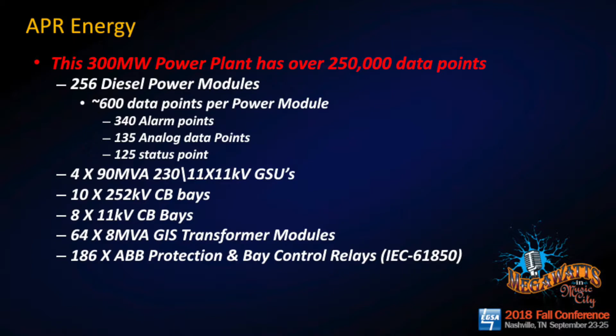Why collect all this data? This is an example of an existing power plant we brought online in August. It's 300 megawatts, with 256 power modules, a mixture of Caterpillar 3516Bs and MTU Series 4000s on the job site. We've got close to 340 alarm points, 600 data points, 135 analog data points - a lot of data - and 4 big power transformers stepping up from 11 kV to 230 kV. I've got 10 252 kV bays to interface my transformers onto the customer's transmission line.